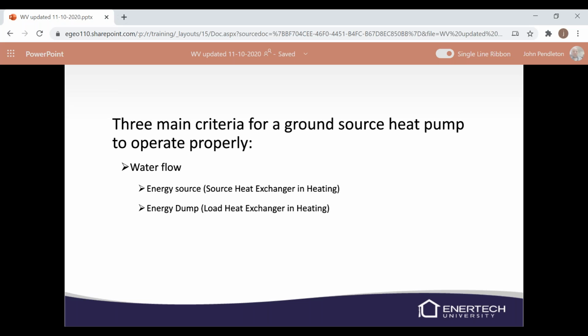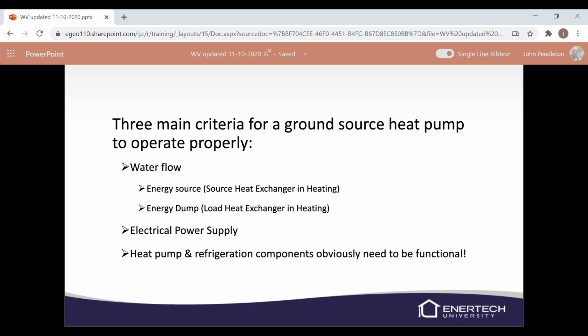This thing's real sensitive to micro bubbles. So just make sure we're sizing piping properly for a good flow, and that we're not trapping air in certain areas. Same thing with the source. Make sure we've got proper loop field, and make sure we're adding a little bit of extra loop for the domestic hot water feature. Got to have power to the unit, obviously, and make sure that the compressors and all your pumps are operating, that everything in the circuit is operating. Can't expect the unit to work real well when our load pump has failed or compressor's not pumping.